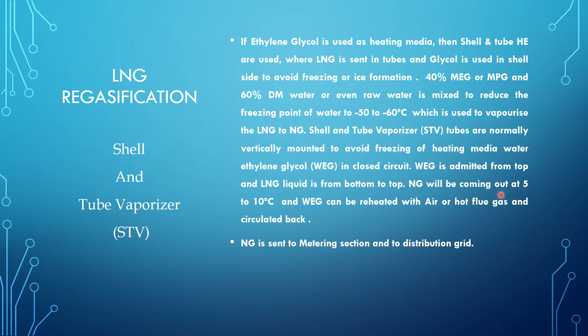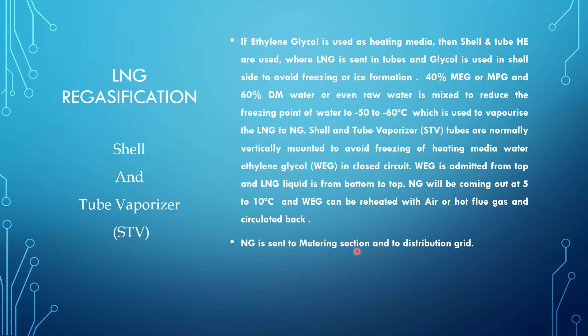The natural gas exits the exchanger at 5 to 10 degrees centigrade. The cooled WEG can be reheated with an ambient air heater or with hot flue gas from furnaces, then circulated back for the next cycle. The natural gas is then sent to the metering section and then to the distribution grid at high pressure and 5 to 10 degrees centigrade for customer usage.